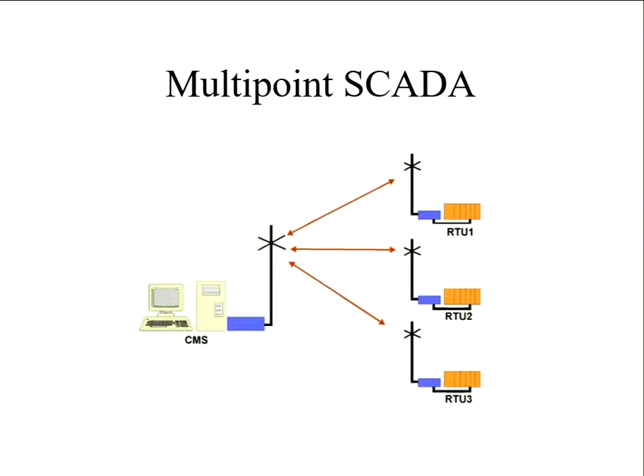And again, there's no direct connection between the slaves, so off-take 1 doesn't talk to off-take 2. They both talk to the centre, and the cycle times are relatively long, because at the end of the day, a lot of the dynamics are the pipeline system dynamics. Pressures across a pipeline don't change extremely rapidly.